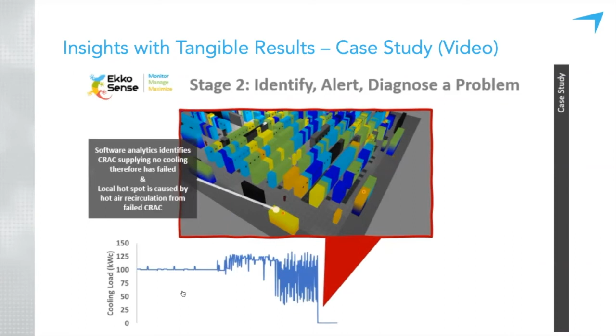We'll just keep rolling. So we have the steady state condition. The AI engine's learned the room. It's understanding the behavior of the cooling systems in there. Later, the software's detected, and it's quite apparent because we're seeing in the analysis data that the output from one of the cooling machines is becoming variable. So its behavior has changed, even though the rack temperatures haven't significantly changed. So it's at that time that the software is starting to issue warnings well ahead of any issue.